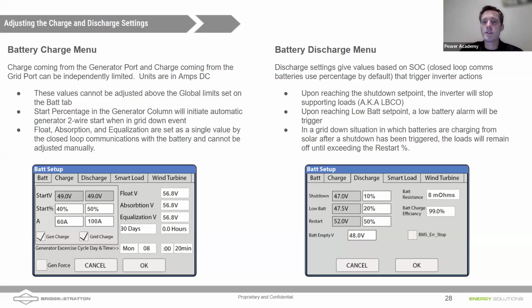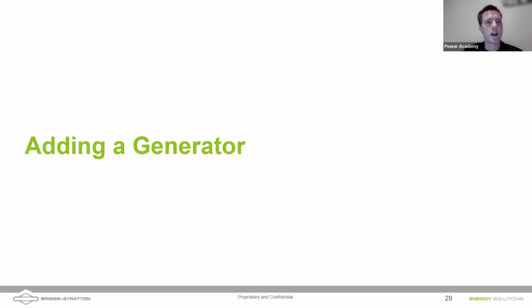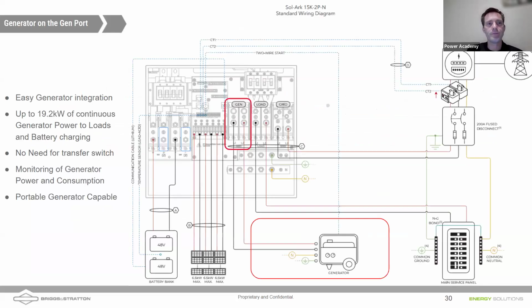So good points. Battery resistance will automatically come through the communications. That should automatically program for you with closed loop communications. Battery efficiency, it's right around 99%. And so that's the value you should program in. Of course, there are some variations in efficiency. If you're doing very fast charges and discharges, efficiency is a little bit lower, but these are highly efficient batteries.